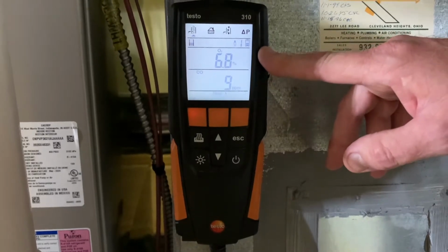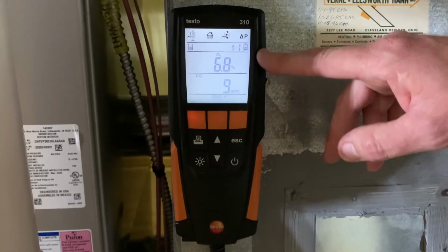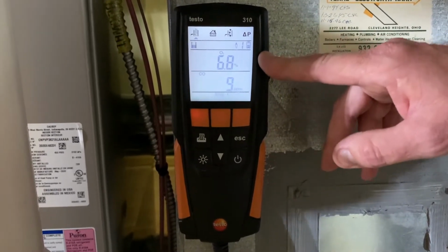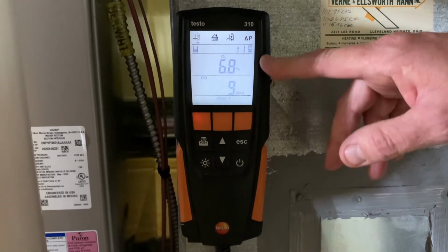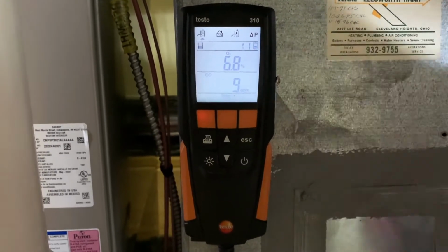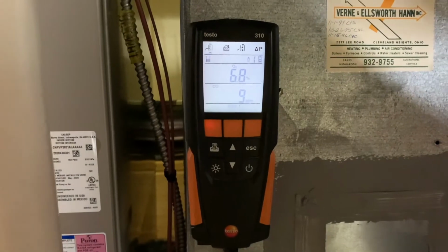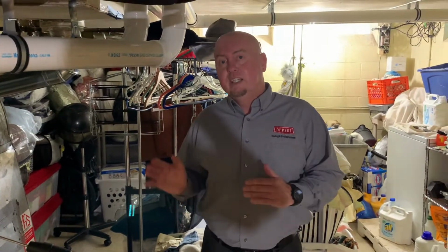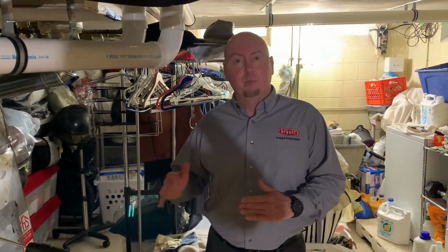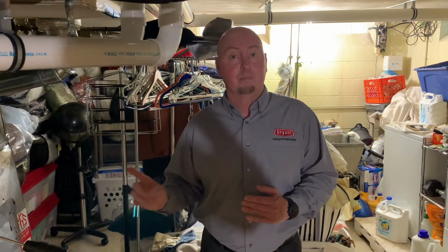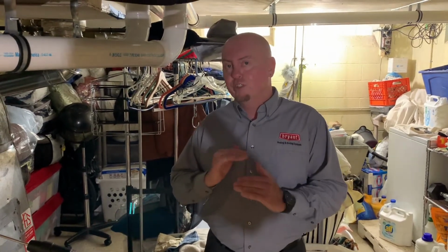If that number keeps dropping on a 90-plus furnace, it goes from 6 to 5 to 4 to 3, that could be an indication the secondary heat exchanger is filling up with water. So you really want to watch that number. That's a really great number to tell you really what's going on in the combustion process. The other thing is, you want to look at that number upon startup. Once you start the piece of equipment up before the blower comes on, that number should stabilize out.